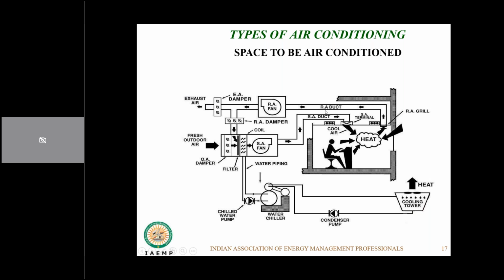So normally in a recirculation system, you have air coming in, and then it goes through the cooling coil. Here you also have some fresh air coming in, so you decide the component of fresh air you want, and you throttle this damper so that the right amount of fresh air comes in. Normally you have a filter over here too, and this mixing of the return air from the room and your fresh air goes through the coil, gets cooled. The supply fan pushes it into the room. It takes away the room heat which is coming from the solar, from the person and the laptop that you are having, and it absorbs this heat, and the cycle continues.